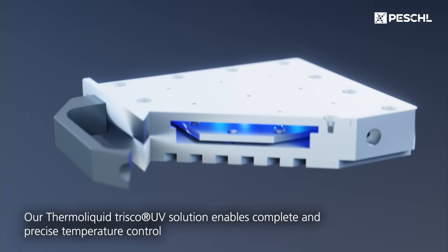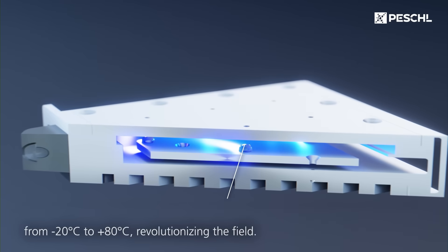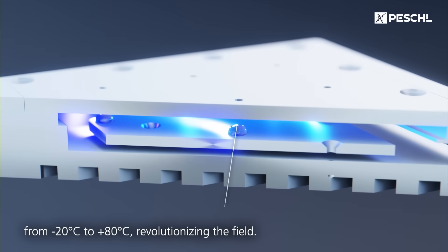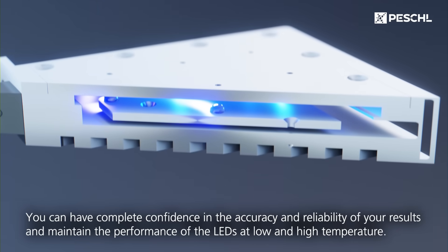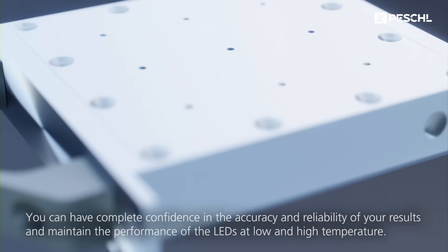Our ThermoLiquid Trisco UV solution enables complete and precise temperature control from minus 20 degrees Celsius to plus 80, revolutionizing the field. You can have complete confidence in the accuracy and reliability of your results and maintain the performance of the LEDs at low and high temperatures.